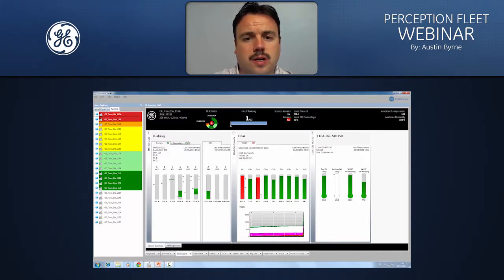You can see here on the screen now I have my device summary dashboard, and the device summary dashboard captures all the critical measurement information that is taken from the transformer. So for this particular example we have a bushing monitor in the form of an Intellix BMT 330. We have a DGA monitor, which is our multi-gas Kelman product, and we have an MO150 as well. Our bushing monitor section shows us the power factor and capacitance changes that are being experienced within the actual unit, as well as the partial discharge index. This is the most recent measurement that is taken from the device, which is displayed in this dashboard.